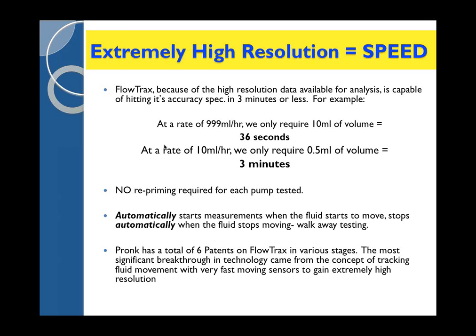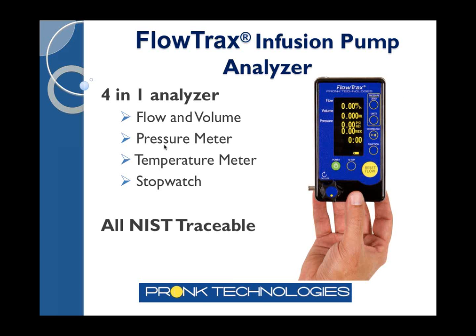With our device, there's no repriming required for each pump tested. It automatically starts measurement when the fluid starts and stops when the fluid stops, so you don't have to stop the analyzer at the end of the test. So just a quick overview, the Trax is actually a 4-in-1 analyzer. It does flow and volume. It's also a pressure meter, and it can measure temperature and has a built-in stopwatch, all of which are NIST traceable.